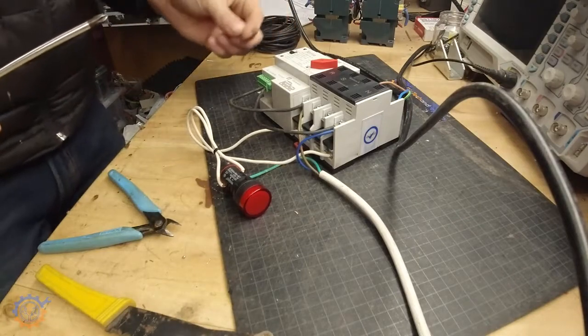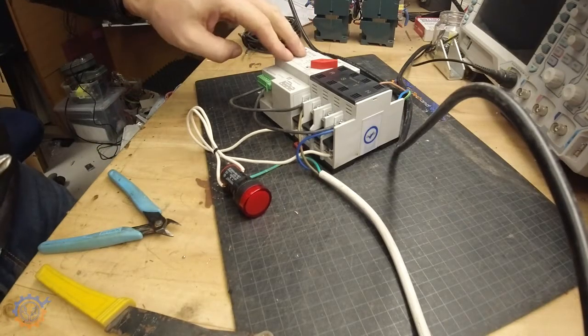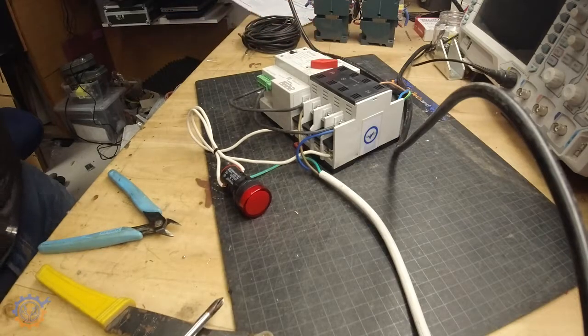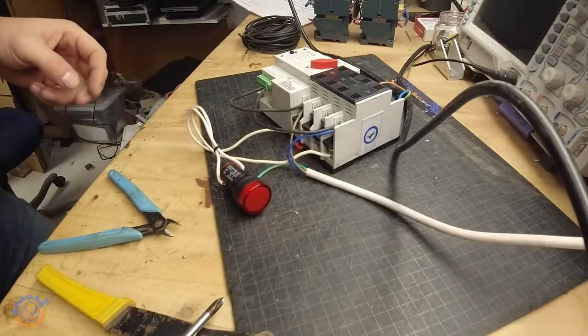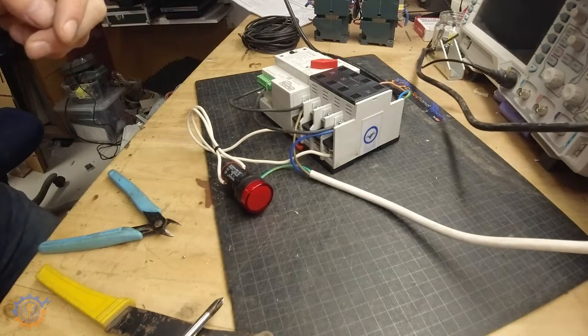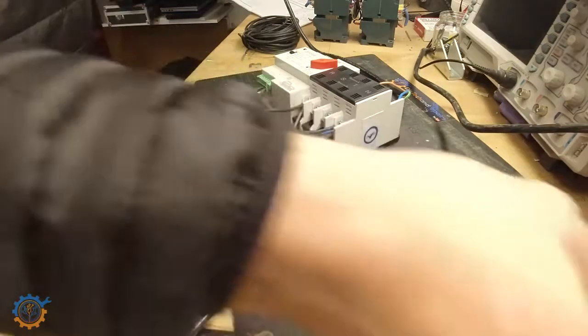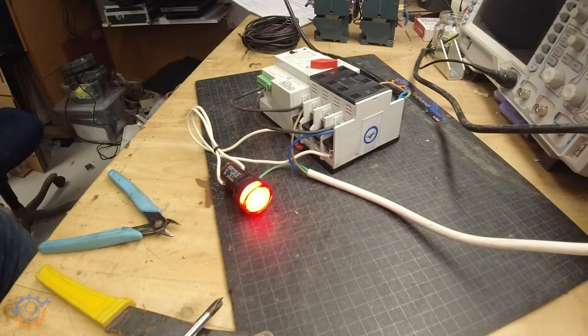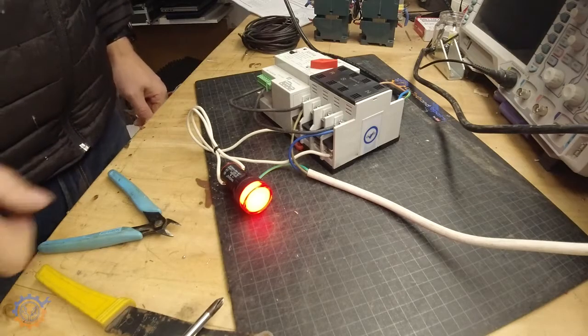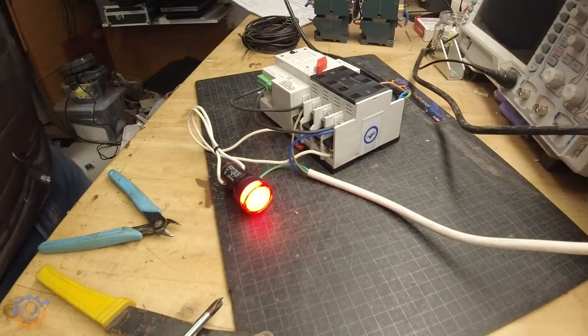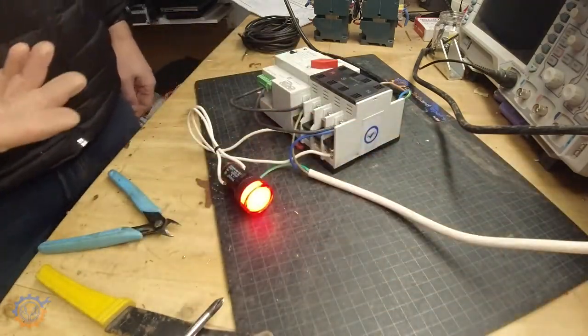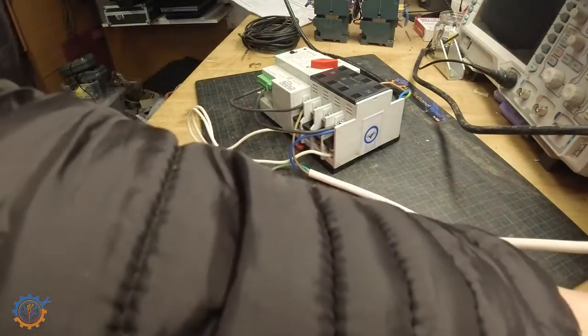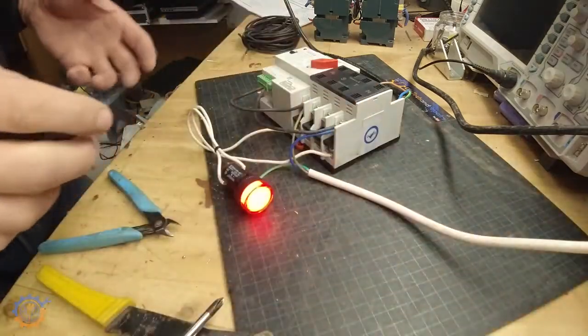So now we have one of the sides hooked up. And potentially when running in auto it should switch and use the B source as the primary source. So let's try that out. I'm hooking up the power again. B is now primary. And A is joined up as well. Let's switch. Now we have the A side active and we hit the B. And we can see that it switched over. But if I kill this again it will not switch back again. So let's hook up the other one.